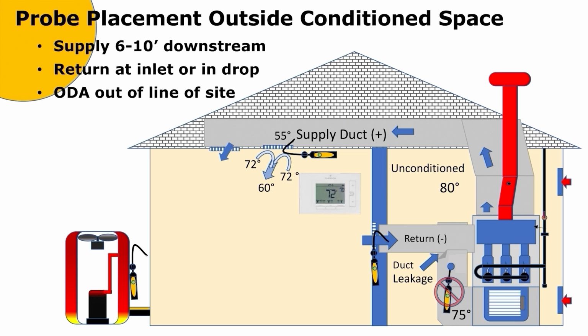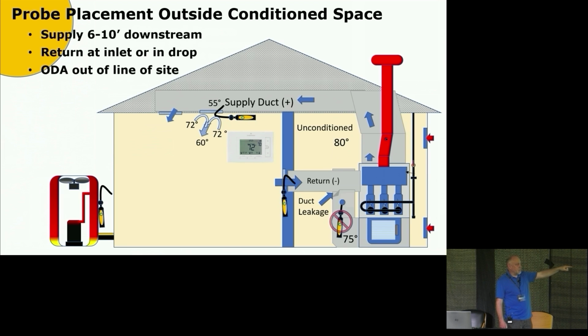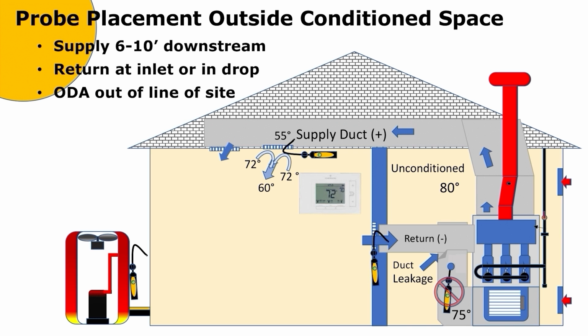If the probes are outside the conditioned space, so what I'm showing here is like a garage, pretty common in Florida, I do not want to be in that return air drop. I want to go inside the house and put that actually at the return, okay? Because we want to test from inlet to outlet on that system. So what we're trying to determine there is if we have duct leakage.